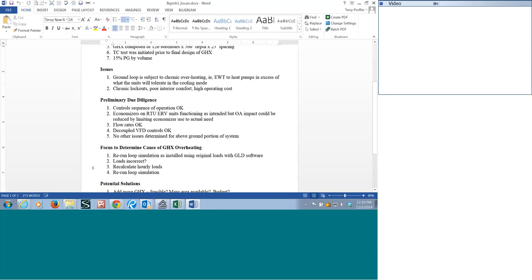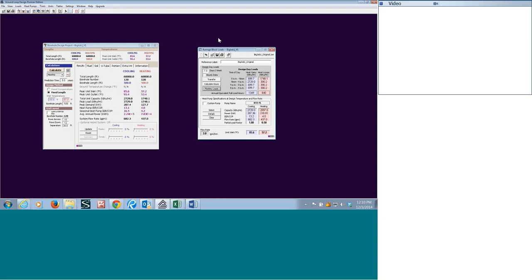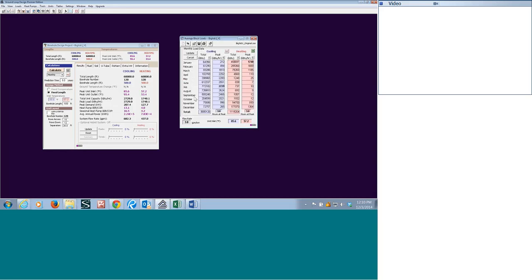One of the first things that I usually do is try to replicate the simulation using GLD, where I'll rebuild the loop field parameters, and if the original loads are available. Sometimes they're not, because if something's contentious, unless a lawyer tells someone to give up the loads, you may not have them. But in this case, we're going to assume that we do have loads. So we're going to go back to GLD here. All we were provided with for this exercise was the monthly load summary of an 8760 hourly load profile. We were not provided the full hourly, so this could have come from eQuest or something like that, where the nominal output is strictly a monthly summary. You can, with eQuest, get the full hourly loads, but unless the operator knows how to do that, they may not be able to get them.